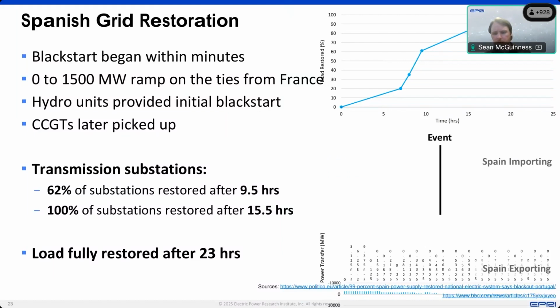For some reason, the chart in the bottom right here is not looking too healthy. But in the original version of these slides, we had a chart showing the flows of power between France and Spain. Basically, we could see within the first 2 hours after the blackout a steady ramp up in power from France to Spain, peaking at about 1,500 megawatts. That happened quite quickly. So they were able to use those megawatts from France to begin re-energizing the grid.